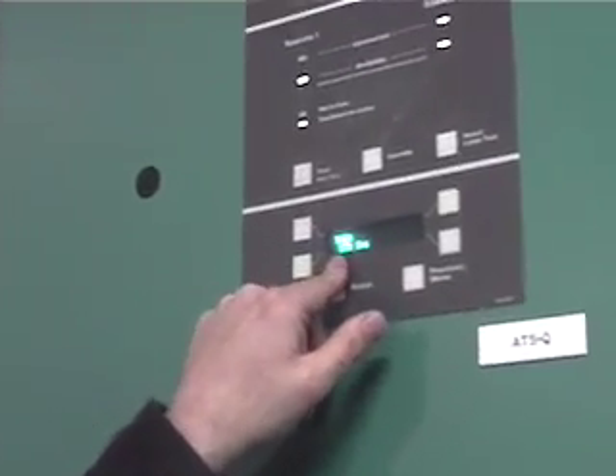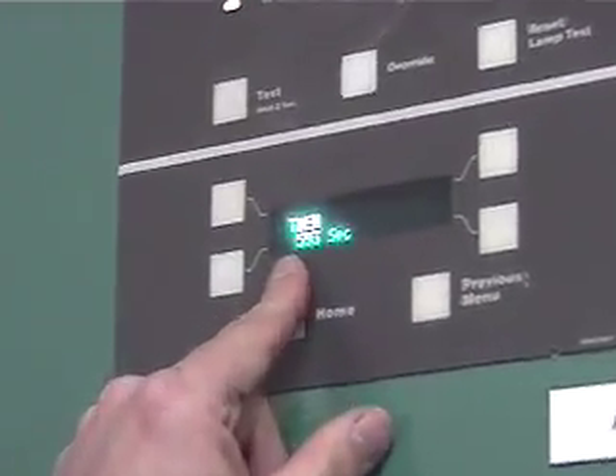Now you see TDEN, that's time delay emergency to normal, our retransfer time delay. It's set up for 10 minutes. If you don't want to wait for that, which I don't like to wait for, especially the cameraman doesn't want to wait for that, you can push the override button to override that time delay.